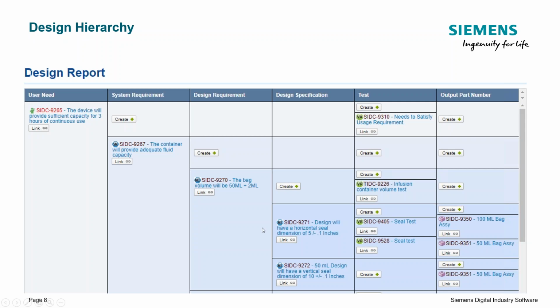This is just a quick report example of how this kind of construction can happen. We have a user need that goes to system design and design specification. So we have a 4-level requirements breakdown, just as an example. And now we have test cases, and those test cases are related to the level of requirement that is required. So you might have a requirement or a test case, a verification test case that's associated with a design requirement or a system requirement. But also we have these validation test cases that are really different in construction. We are going to be testing the finished device with end users rather than sort of bench testing. That's more along the lines of verification testing.